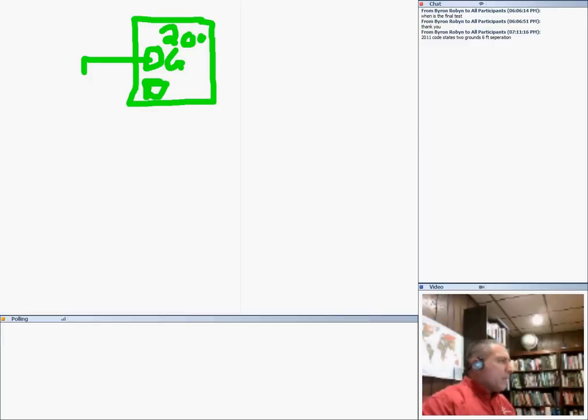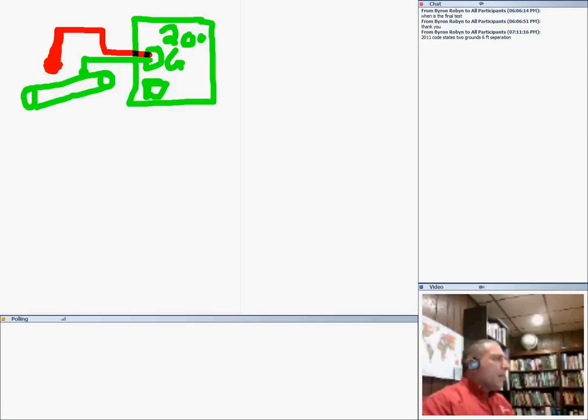In residential, guys, here's my 200 amp panel and my ground. Here's my neutral. I'm just interested in the ground. Come over here. Here's my water system coming to my building. Now this is where I tie to my water, because it's a pipe. I need to supplement it with another one. So when you supplement it, you supplement it with a ground rod, right into the earth. So either a ground rod or a pipe. If you have a pipe or a ground rod, you supplement it. Any questions about supplementing with a ground rod or a pipe?